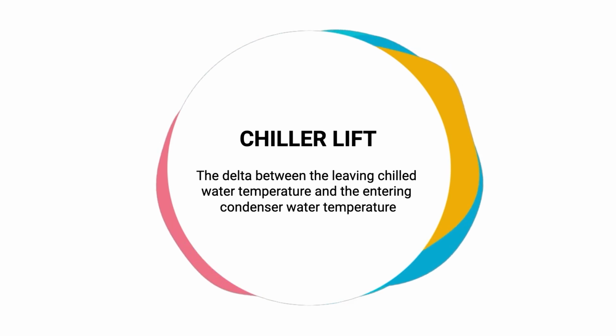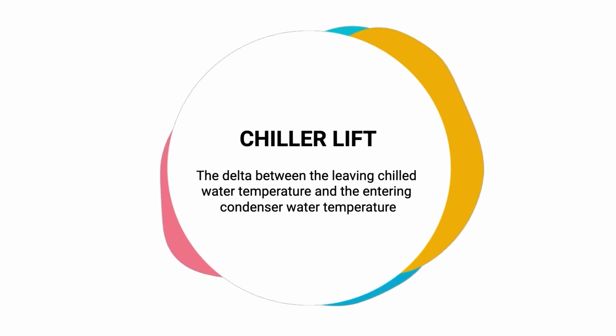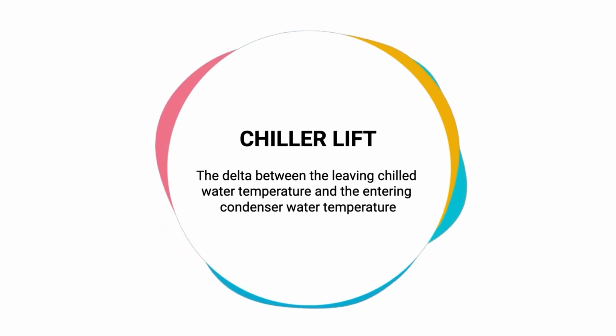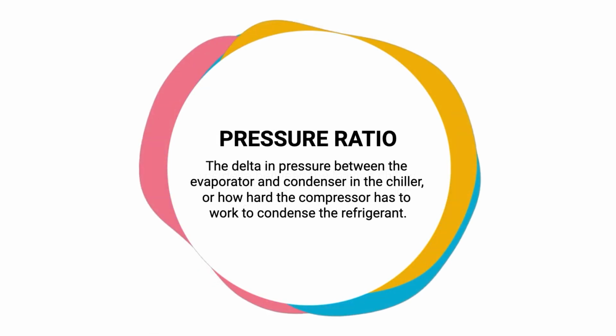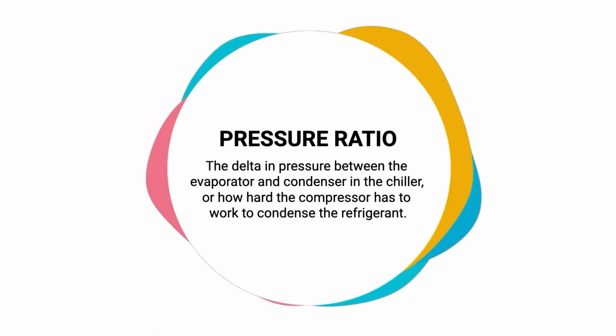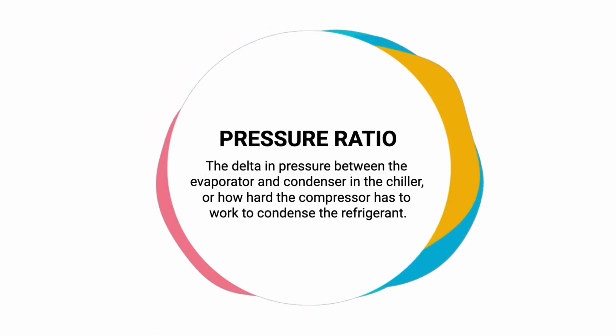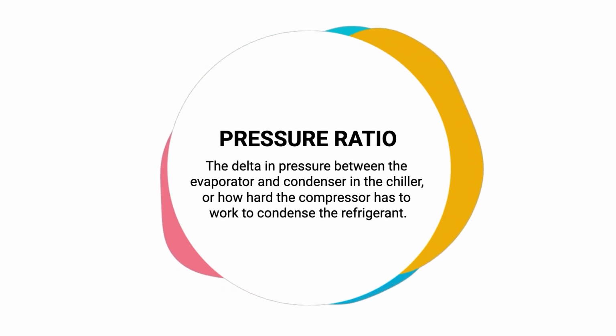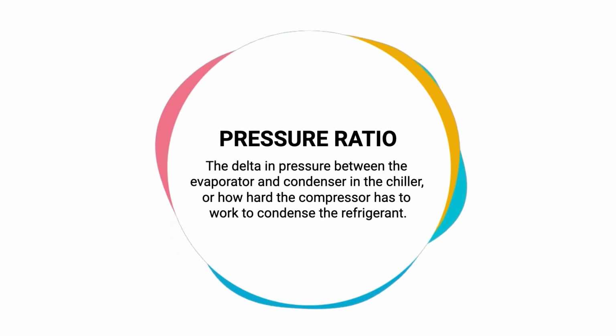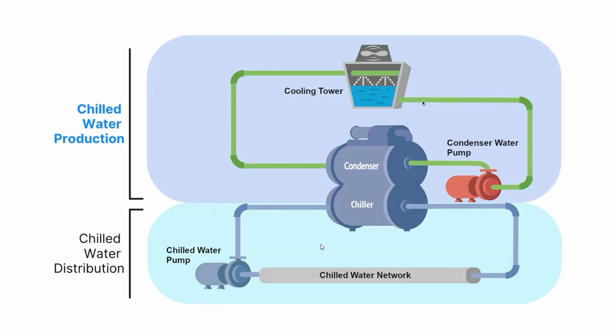the compressors, that difference between condenser water temperature and chilled water temperature is lowered, which means the pressure ratio inside of the chillers is lowered. Those compressors have to do less work to transfer that heat. And in an ideal world, in a well-optimized system, the drop in chiller energy resulting from that drop in temperature is higher than the increase in fan energy.